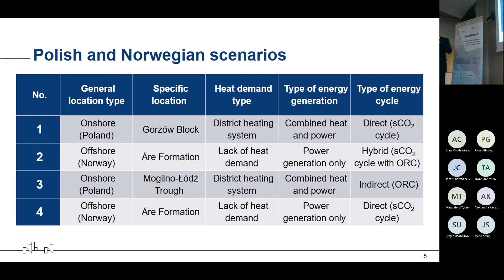I'll start with the 2 basic concepts for utilizing the excess heat from the EGS system. First is the 2-stage expansion with heat export: there's a possibility to export part of the heat into the district heating system, so we're talking about cogeneration, though it can operate without this. We have a direct supercritical CO2 turbine, then a mixer which gets the CO2 makeup flow, then the gas cooler and the injection well, closing the cycle.